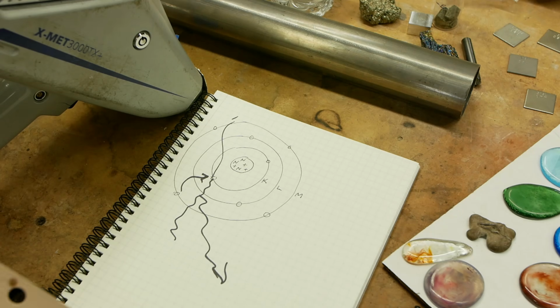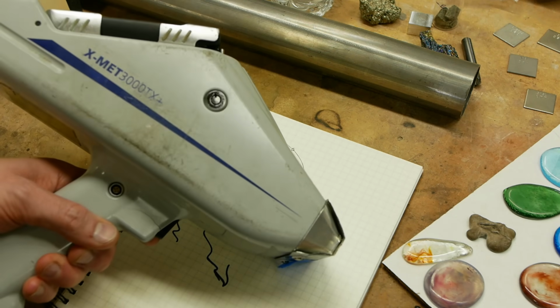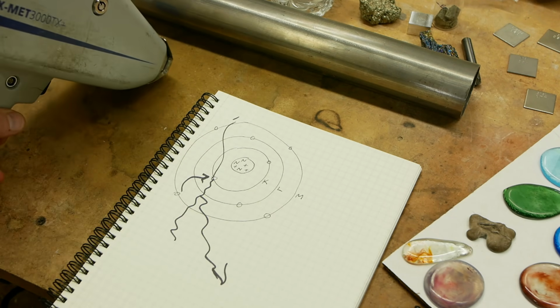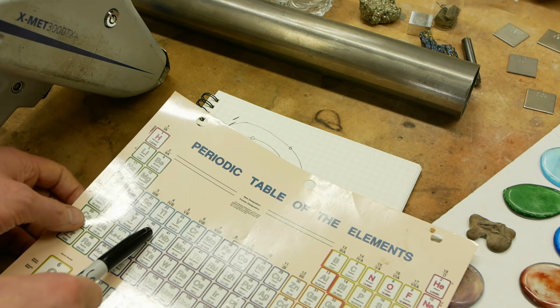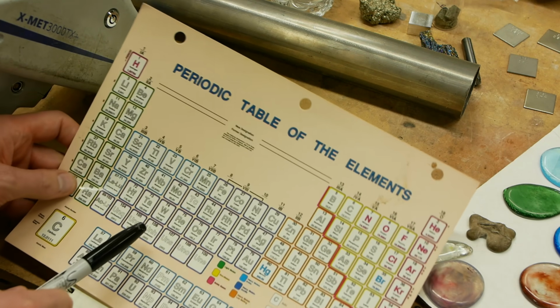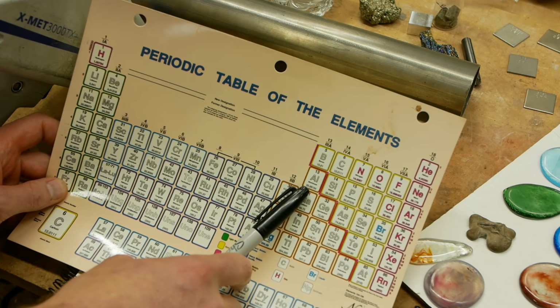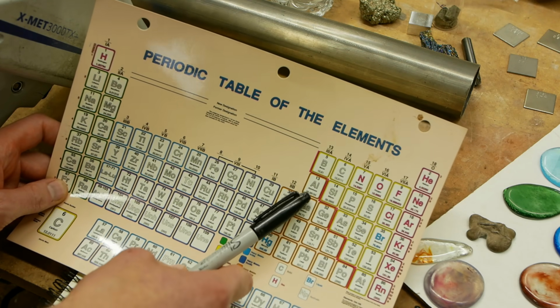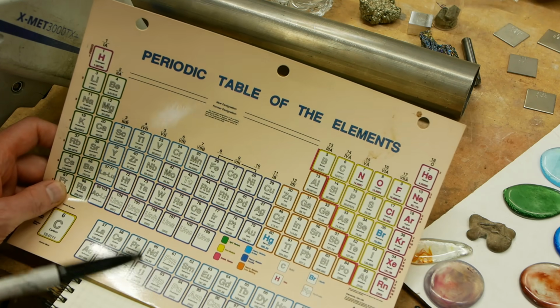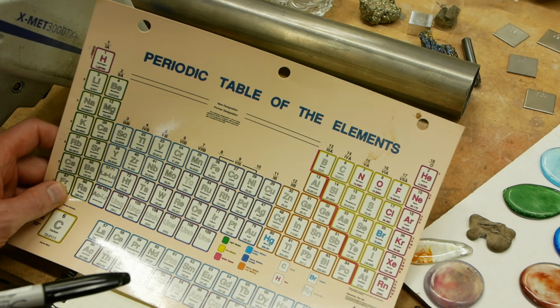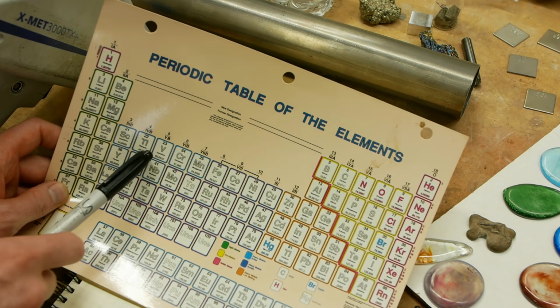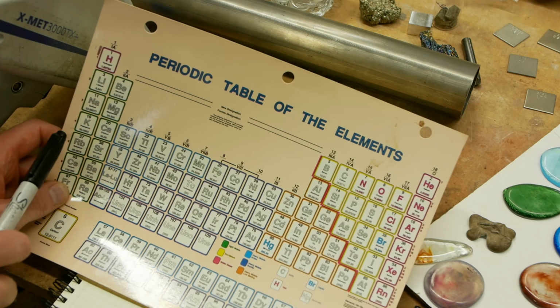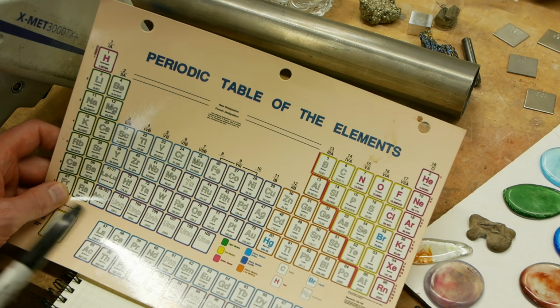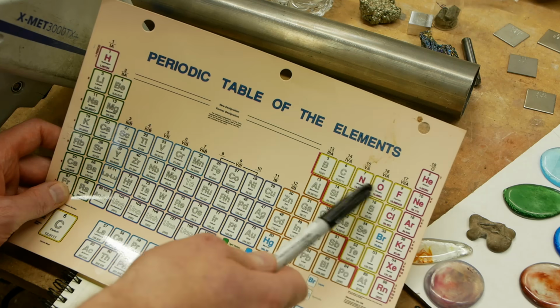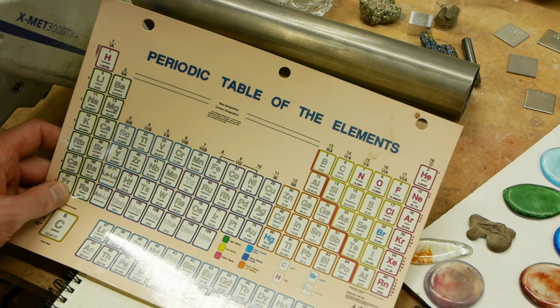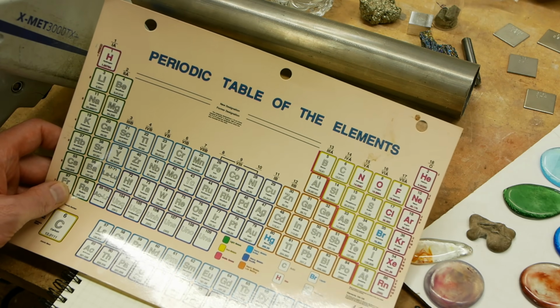And we can't detect it. So this gun is not a particularly new model, and it's only able to detect things that are heavier than somewhere around titanium. So if you're looking at a sample of aluminum, the gun actually does not detect the aluminum at all, but it can sometimes tell you what alloy you're looking at based on the trace element analysis. But it actually doesn't see aluminum. In fact, anything lighter than about titanium is essentially no signal. This could be good. I mean, if you ignore oxygen, that's fine because you may not care about oxygen in your sample. You're mostly interested in the base metals.